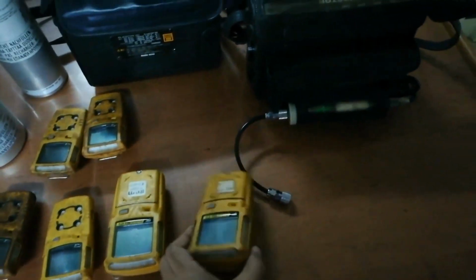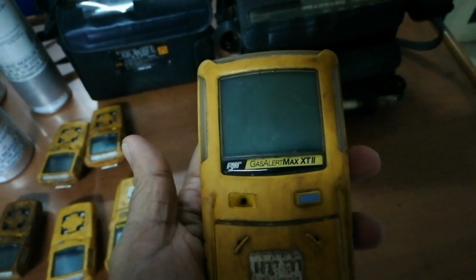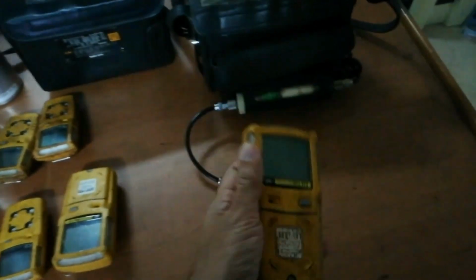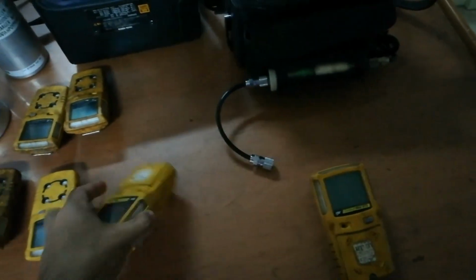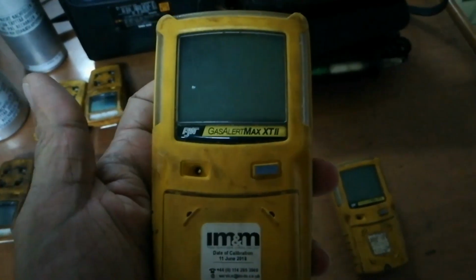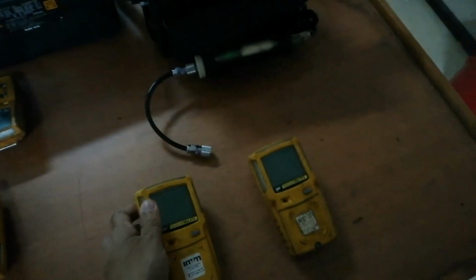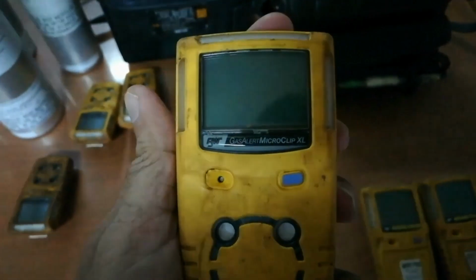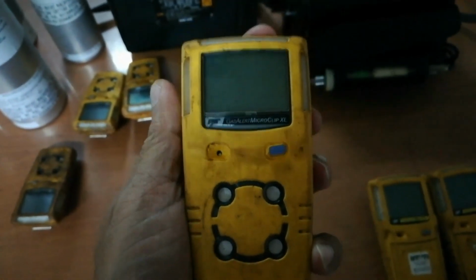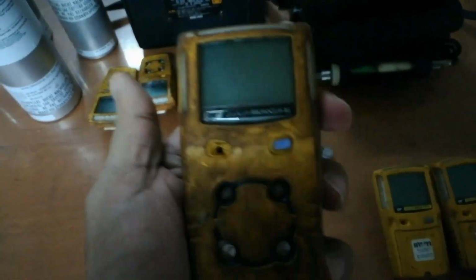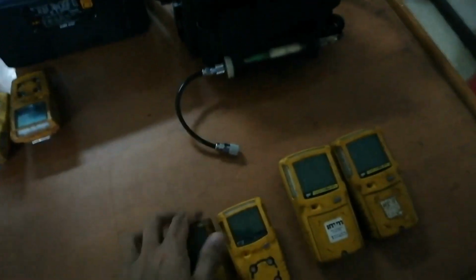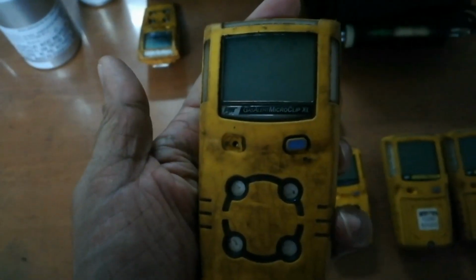Hello guys, here we have three different types of gas detectors. The first one is the Gas Alert Max XT2 multi-gas detector. I have two units of this multi-gas detector, and here we have another four sets of multi-gas detectors. We call it the Gas Alert Microclip XT multi-gas detector. I will show you how to do the calibration for each of these multi-gas detectors.